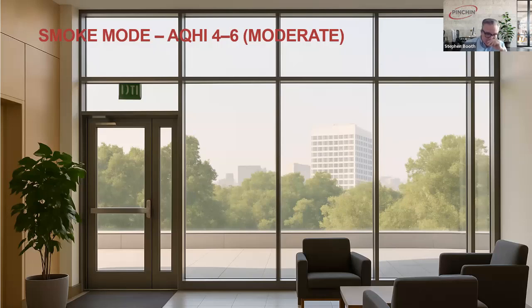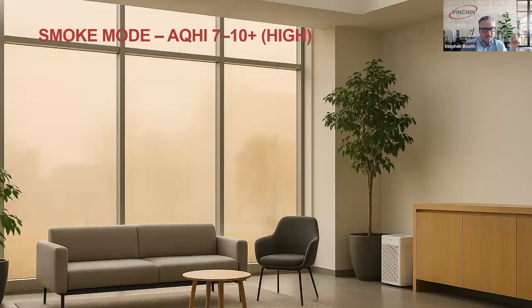What's coming up? And at this point in time, thinking about occupant communication. So, emails or portal notifications that smoke mitigation measures are in effect. And we might want to highlight that these sensitive groups may be more at risk. And we can get all that information really from Health Canada's AQHI index, because that will be listed there. And then we start to get into the 7 to 10 range. We want to escalate those mitigation procedures. Really, as much as possible, we want all our ventilation in recirculation mode only.